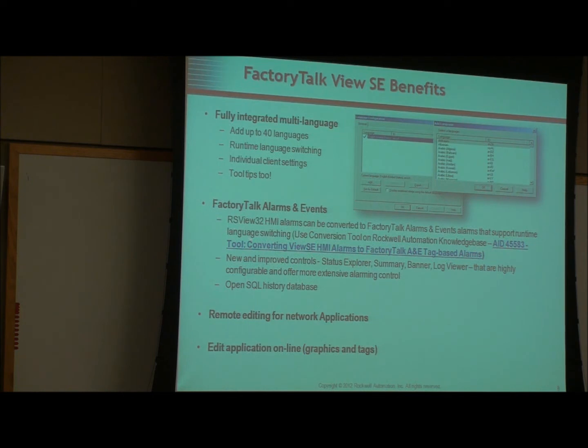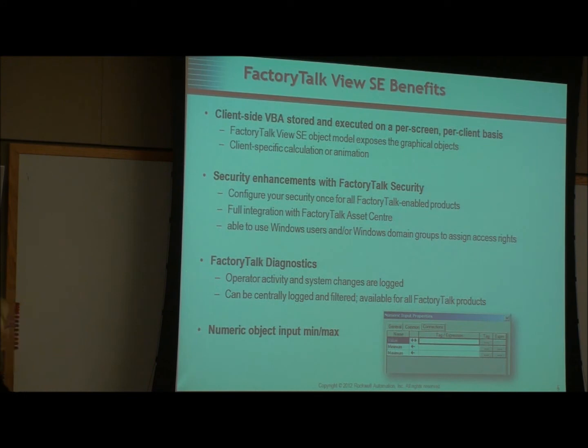You have FactoryTalk Alarms and Events. In traditional RSView32 and traditional HMI systems, all the alarming is done up at the HMI level, and the HMIs are all going, who's got alarms, who's got alarms. Well, FactoryTalk Alarms and Events basically puts the alarming down at the controller level, and the controller says, I have an alarm, and anybody who subscribes to it gets that alarm. So it's a more efficient way of doing alarming, so that you have one guy saying, I have an alarm, as opposed to 12 servers or HMIs saying, who's got an alarm, who's got an alarm. So it moves it down to the controller, and there are quite a few advantages to moving to SE.